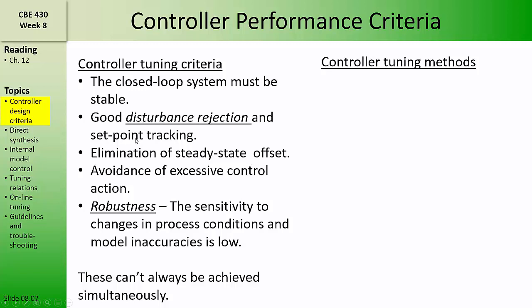Similarly, very tight control — that is, obtaining excellent disturbance rejection and setpoint tracking — may result in controller tuning parameters that are not very robust or that cannot tolerate changes to the operating conditions without becoming unstable. Good disturbance rejection and setpoint tracking may require that we tune a controller very close to a stability limit.